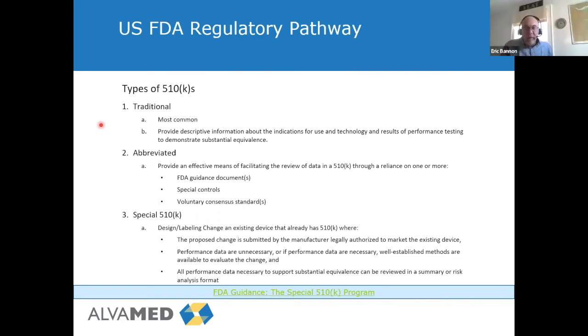So Eric, did you want to? Yeah, just a couple of comments here. One is the abbreviated came about when the FDA was struggling with resources and review times were very lengthy. They added this in to allow companies to say, I'm not going to give you testing, I'm going to specifically claim compliance to a standard, and you can claim that compliance and not provide your testing. That was the genesis of it, but I'm with Martha. I've done maybe four or five of these in my career. It's not very relevant at this point, especially for newer companies entering the market. Generally, you start with a traditional 510K.